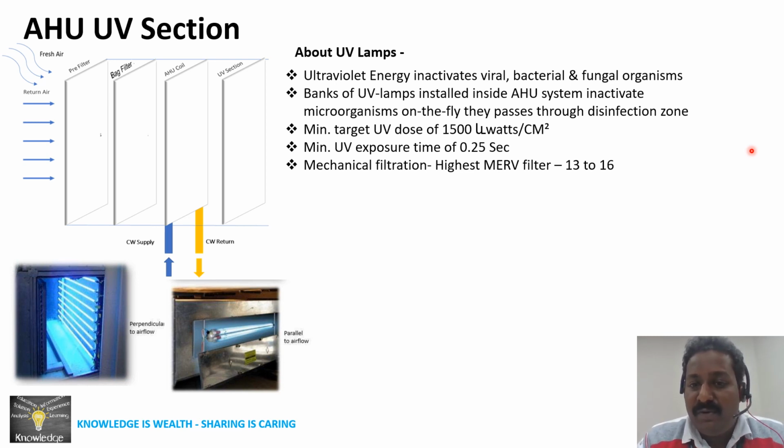The key point to be noted when installing UV lamps, as we already discussed, is that ultraviolet energy inactivates viral, bacterial and fungal organisms. So a bank of UV lamps installed inside an AHU setup will inactivate microorganisms on the fly. That is a very important phrase, on the fly. As they pass through the disinfection zone from the coil section to the fan section, it will inactivate the microorganisms in the air. For that, it needs to operate very quickly.